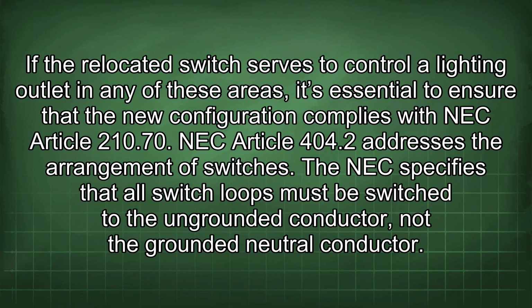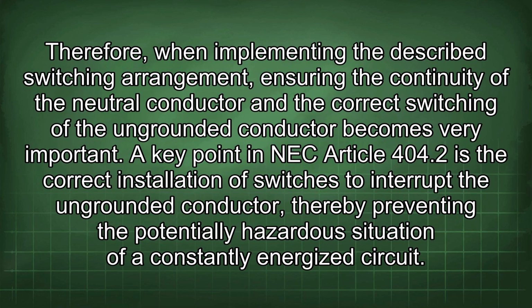NEC Article 404.2 addresses the arrangement of switches. The NEC specifies that all switch loops must be switched to the ungrounded conductor, not the grounded neutral conductor. Therefore, when implementing the described switching arrangement, ensuring the continuity of the neutral conductor and the correct switching of the ungrounded conductor becomes very important. A key point in NEC Article 404.2 is the correct installation of switches to interrupt the ungrounded conductor, thereby preventing the potentially hazardous situation of a constantly energized circuit.